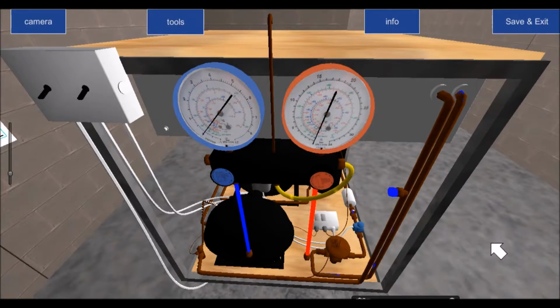So what used to happen is the contractor used to say, well, we'll just top it up. We'll just add a little bit more refrigerant into it to keep it going. And in 6 months' time, that pinhole will get bigger, and over time it'll get bigger to a point that it'll be running short of gas a lot sooner. So instead of running short of gas every 6 months, it will start running short every 3 months, or every week, or it might get big enough that it'll start running short of gas the minute we put it in. And then that means we can find it. In other words, the less time it holds its charge, the bigger the leak, therefore the easier it is for us to find it. Now that is a highly illegal practice.